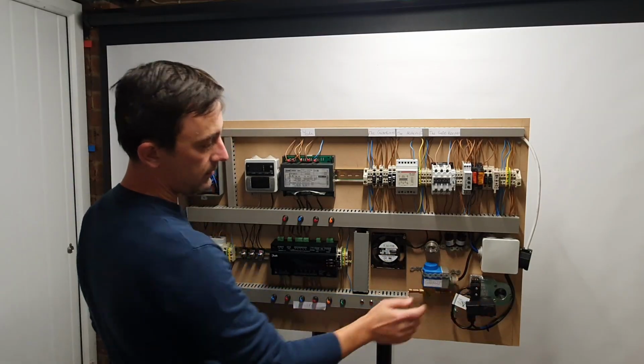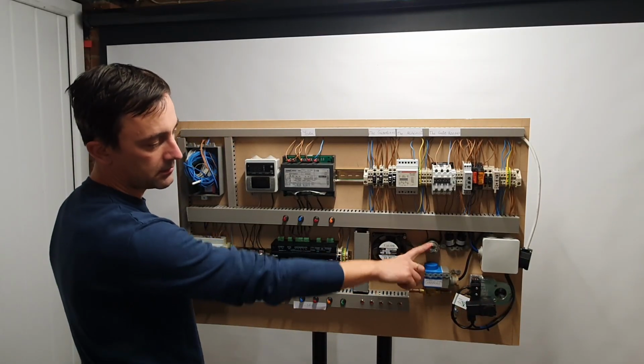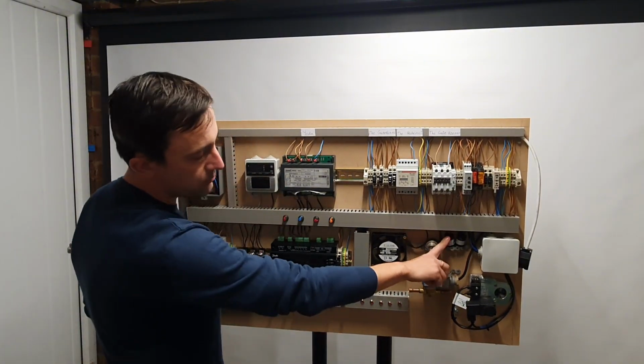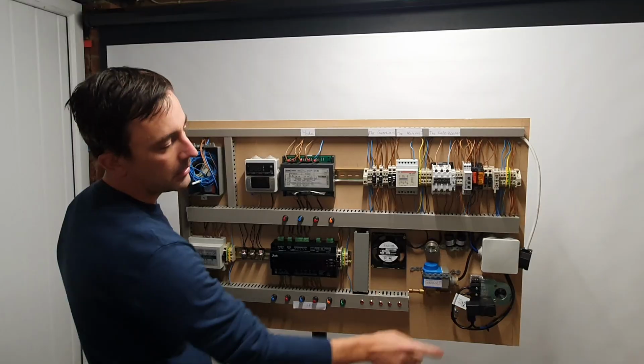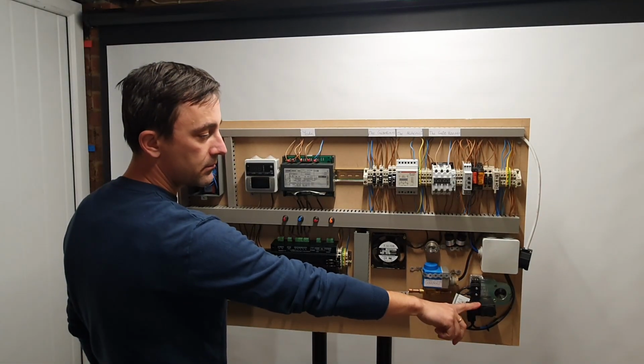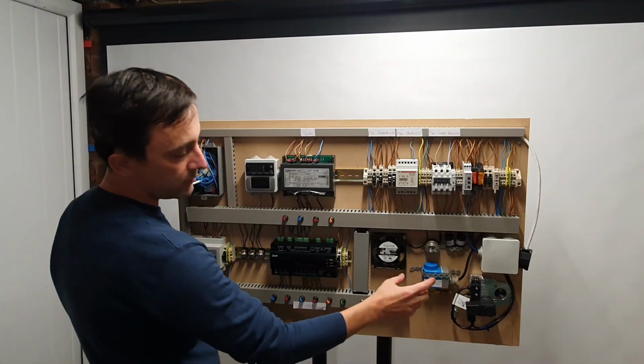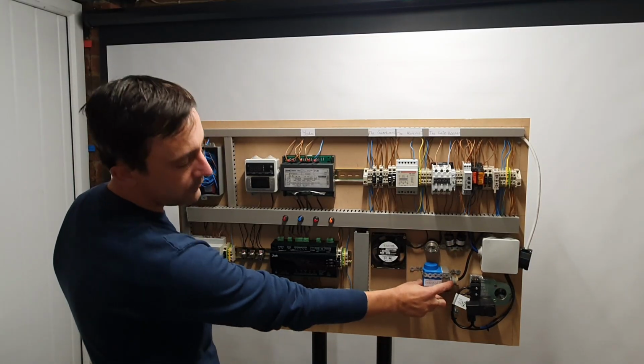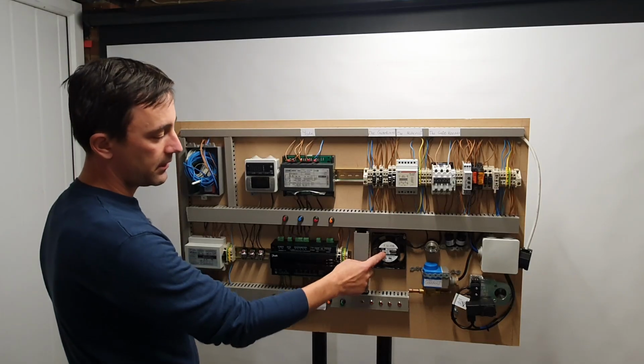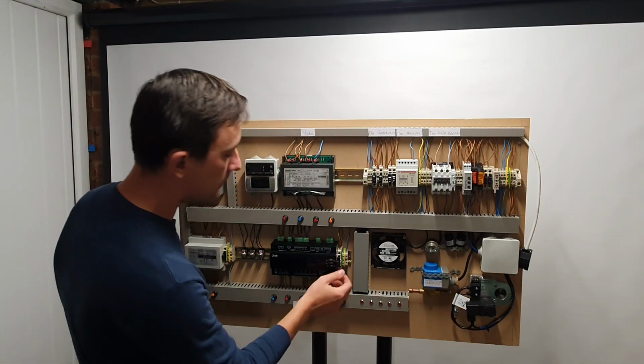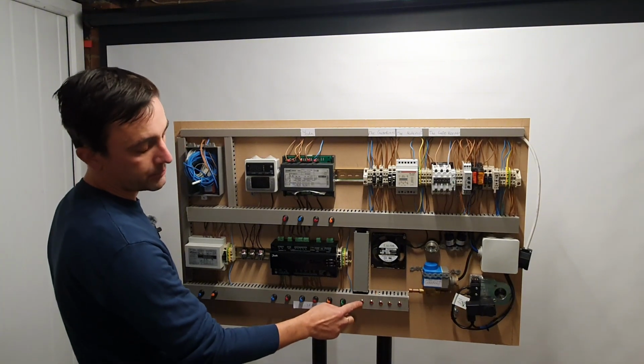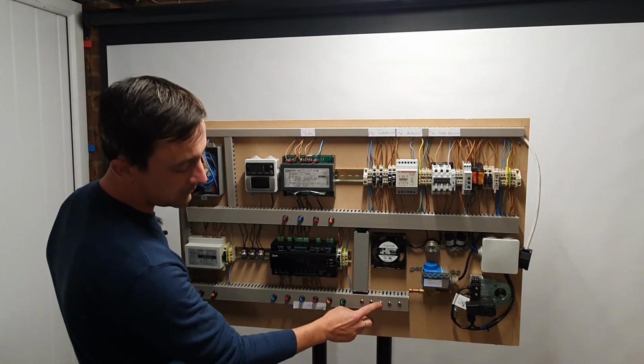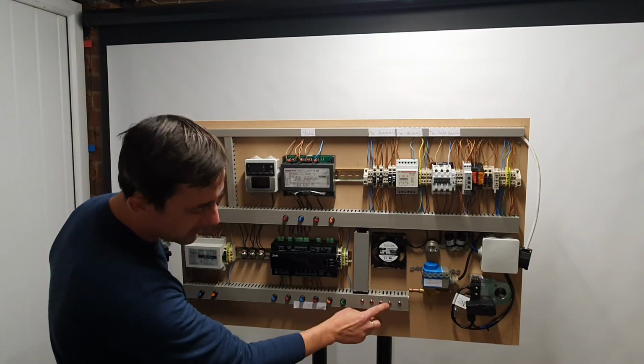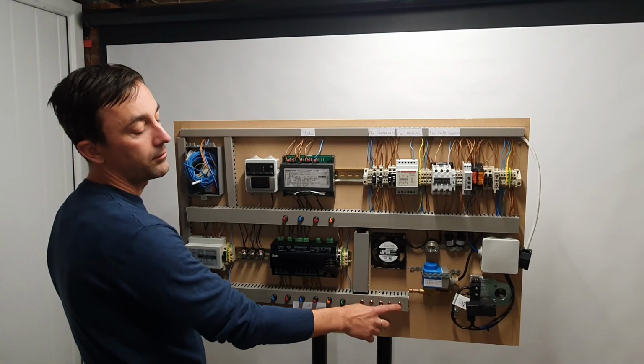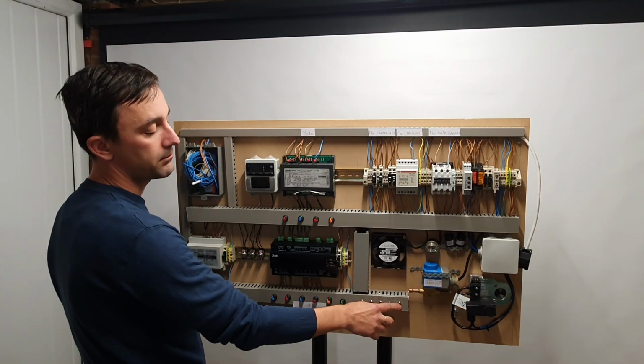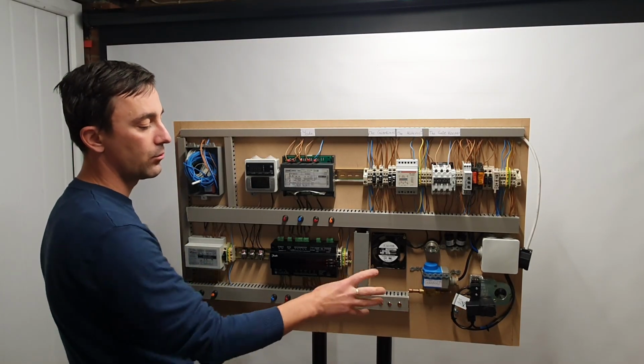We've got a safety circuit. So this is a discharge temperature Klixon. This is an HP switch. This is an LP switch. This is an oil management system, Emerson Traxoil. This would be our liquid line solenoid valve. This would be our evaporator fan. Lights. This would be our compressor number 1, compressor number 2, defrost, a trip light, and an EV light, which is an electronic expansion valve simulating the way it opens and closes.